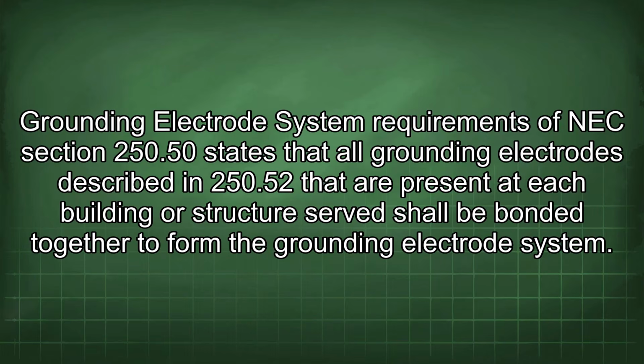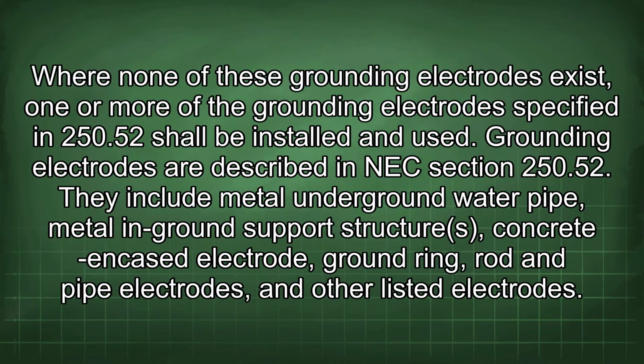Grounding electrode system requirements of NEC Section 250.50 states that all grounding electrodes described in 250.52 that are present at each building or structure served shall be bonded together to form the grounding electrode system. When none of these grounding electrodes exist, one or more of the grounding electrodes specified in 250.52 shall be installed and used. Grounding electrodes are described in NEC Section 250.52.